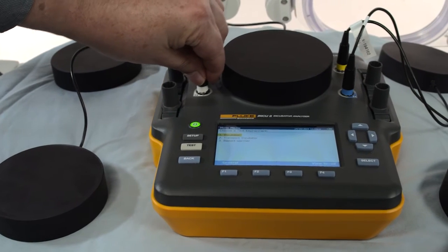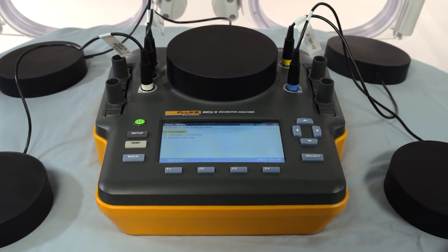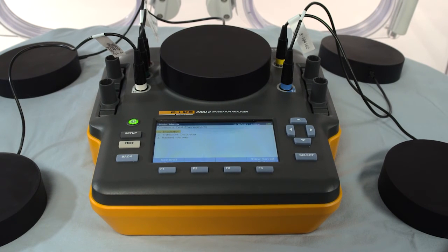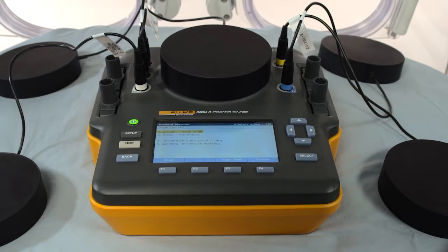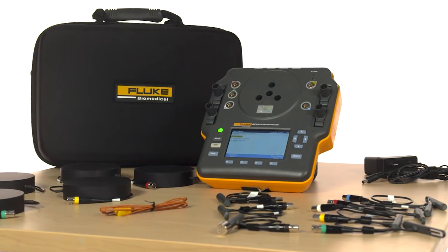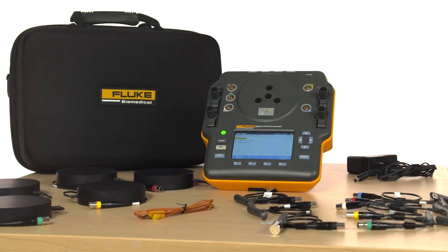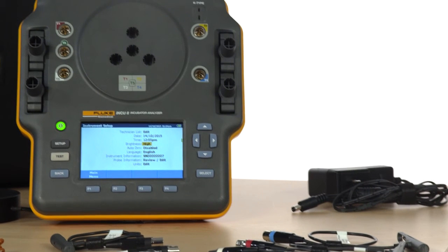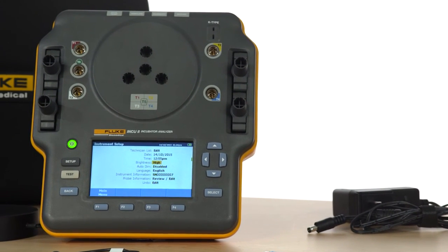To test radiant warmers, simply replace the temperature probes with the radiant pucks. Position them around the warmer according to the standard, then select the appropriate test and testing environment. We've designed the INCU II to not only be highly portable and easy to use, but give our customers a best-in-class, all-in-one solution. The INCU II is compliant with all global IEC standards for radiant warmers, incubators, and transport incubators. Learn more about the INCU II by visiting flukebiomedical.com.